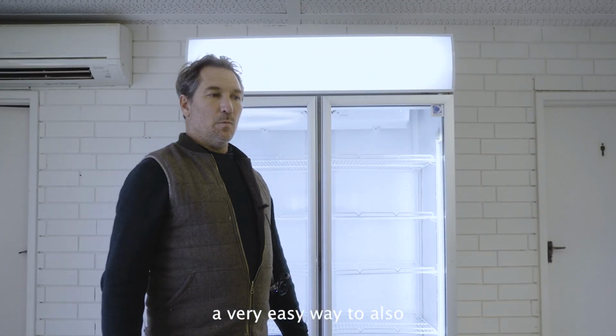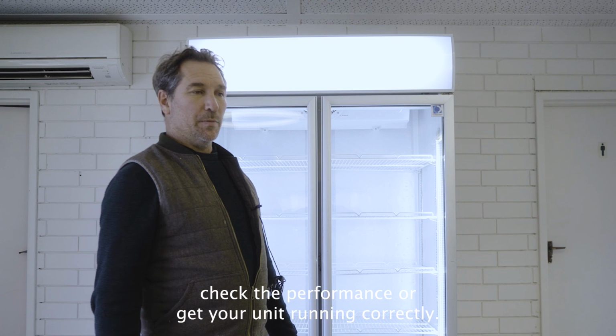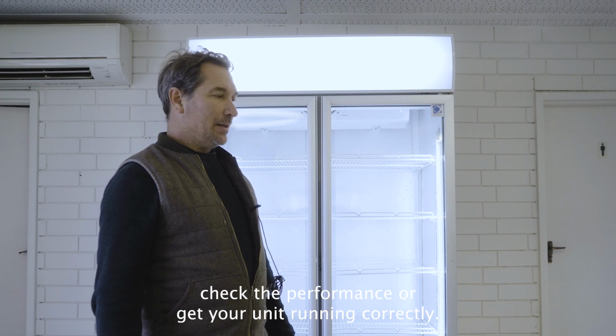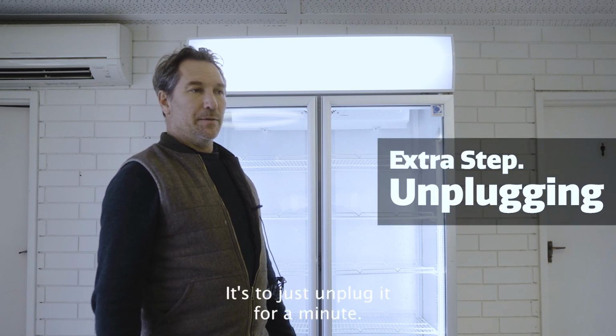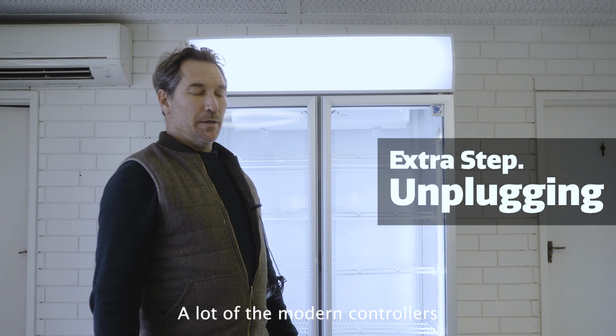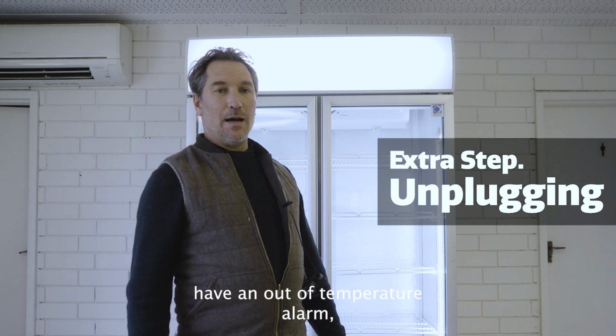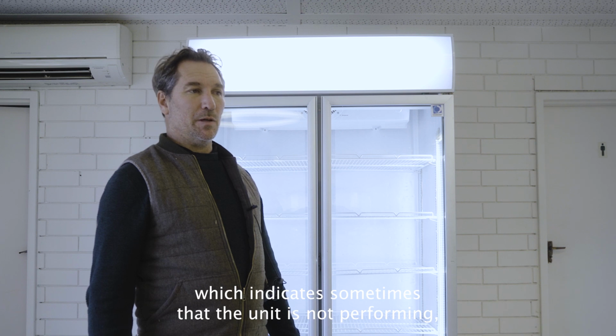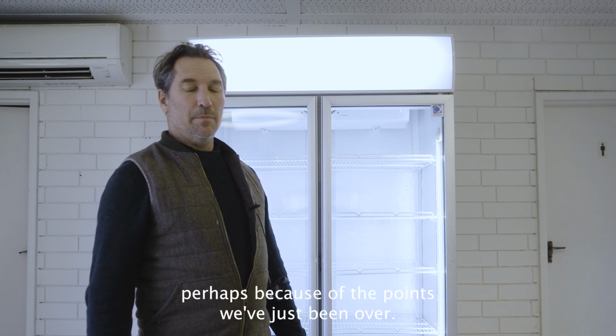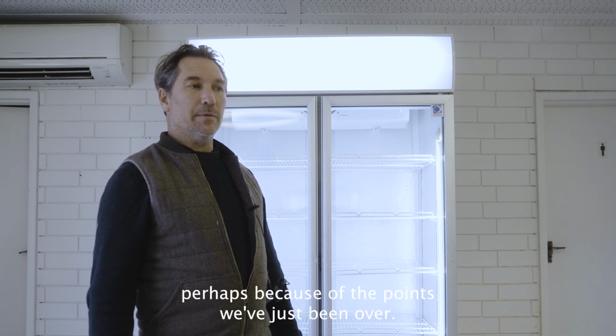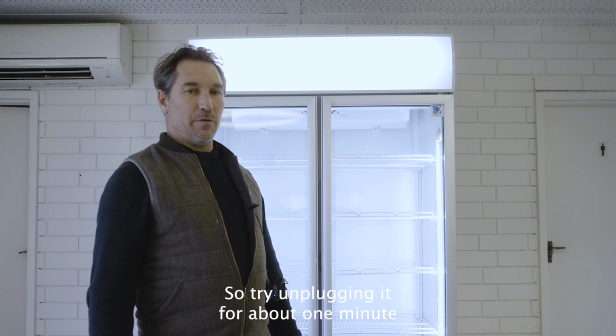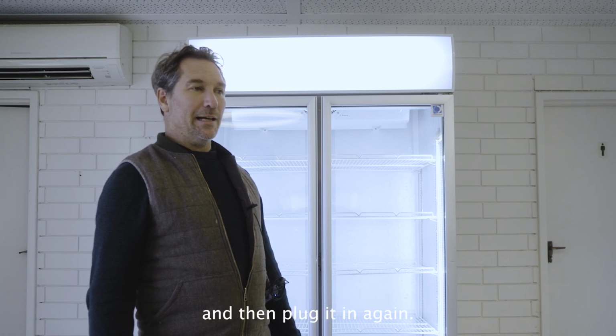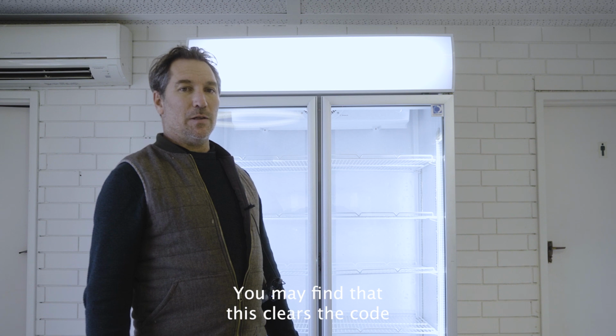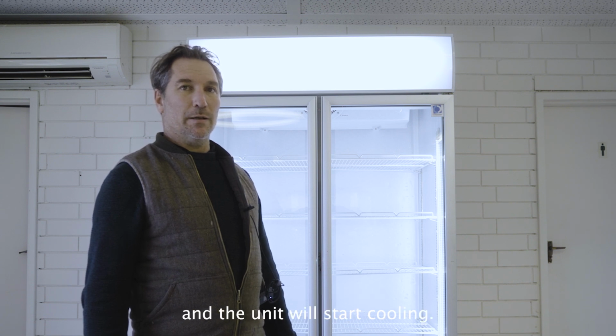A very easy way to also check the performance or get your unit running correctly is to just unplug it for a minute. A lot of the modern controllers have an out of temperature alarm, which indicates sometimes that the unit's not performing, perhaps because of the points we've just been over. So try unplugging it for about 1 minute and then plug it in again. You may find that this clears the codes and the unit will start cooling.